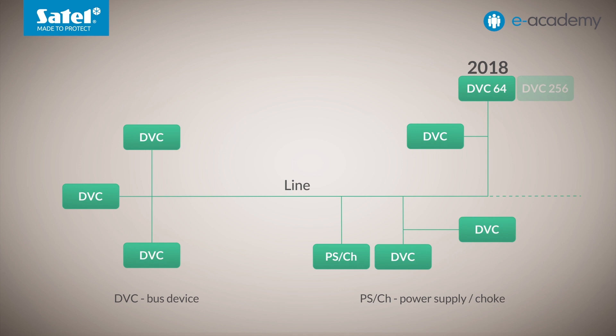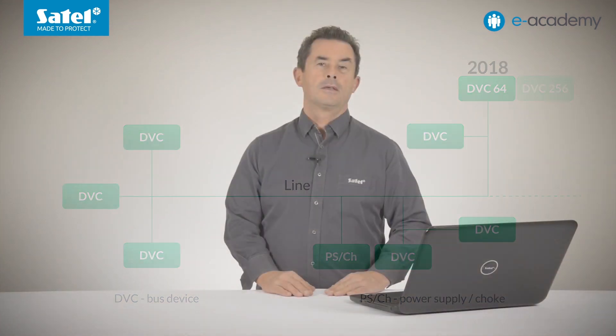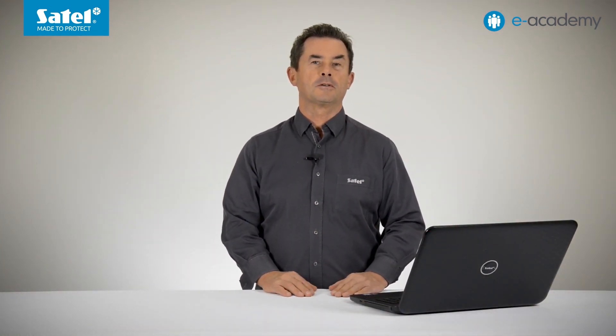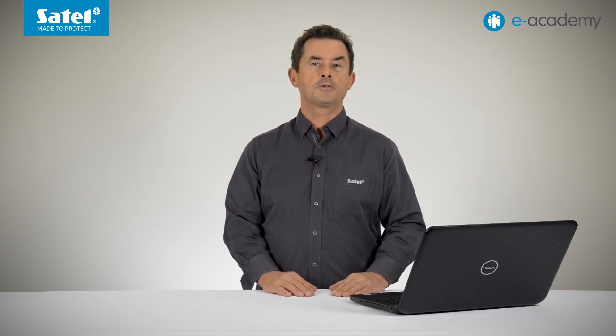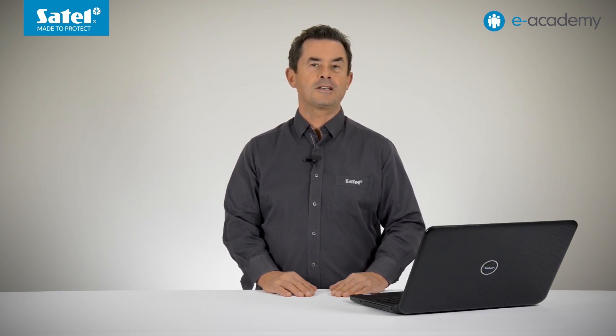At that time, the main line segment could be extended by three more segments. The line repeaters had to be subtracted from the total number of devices in the line, and of course additional power supplies had to be added there too. So this is what it was like until 2018. As I said a moment ago, currently 256 bus devices can operate in one line.